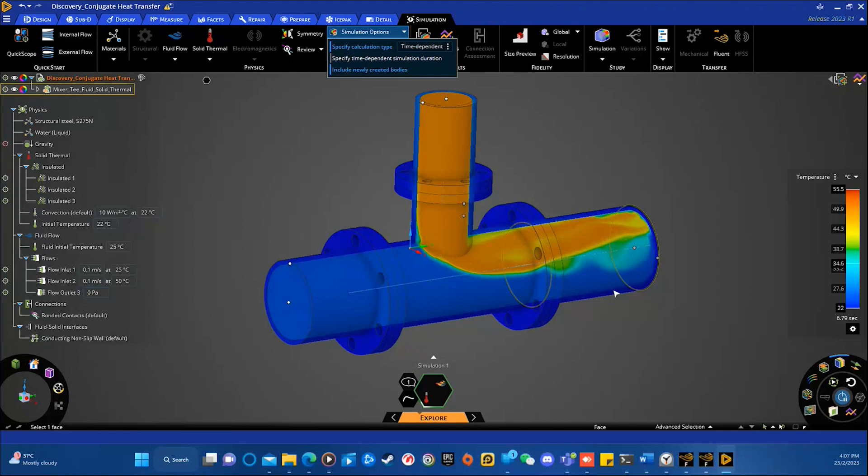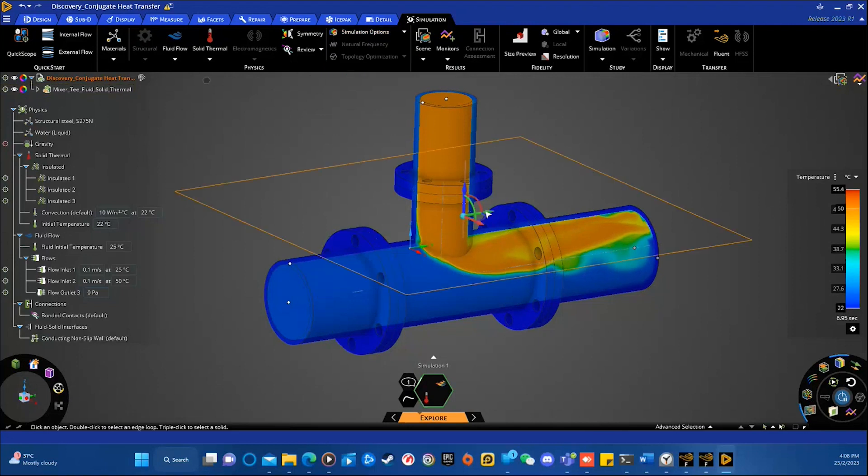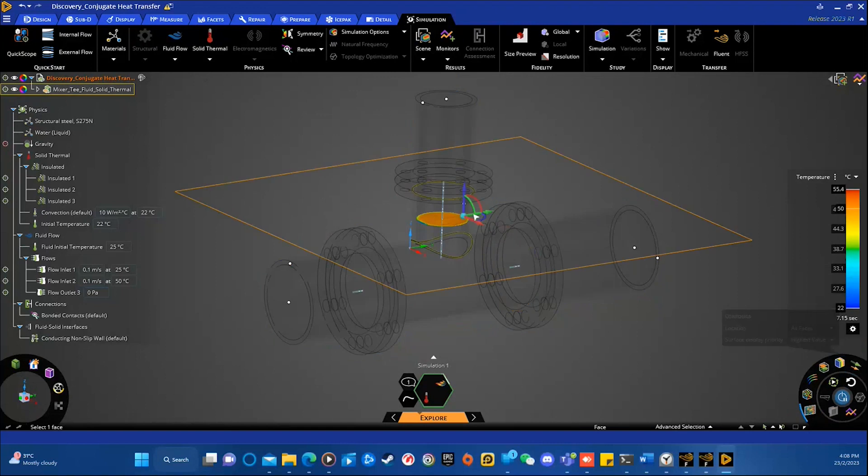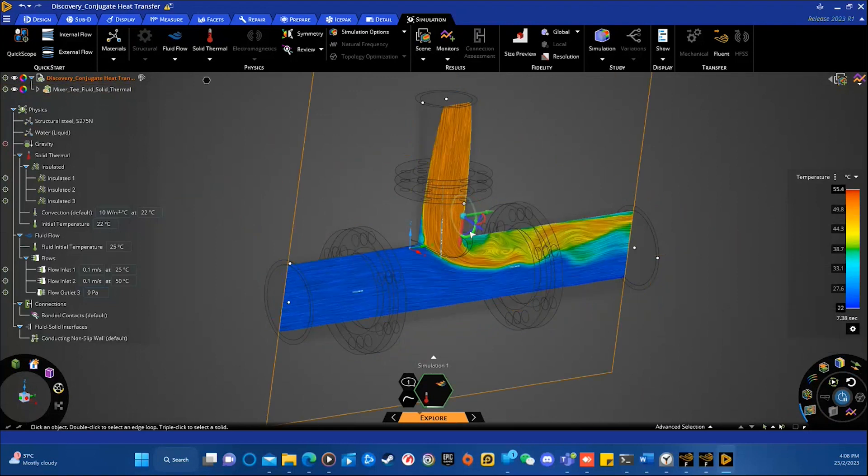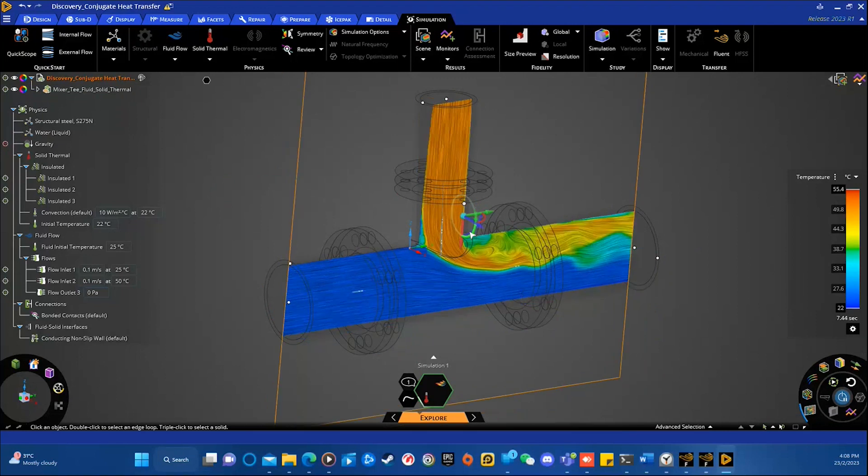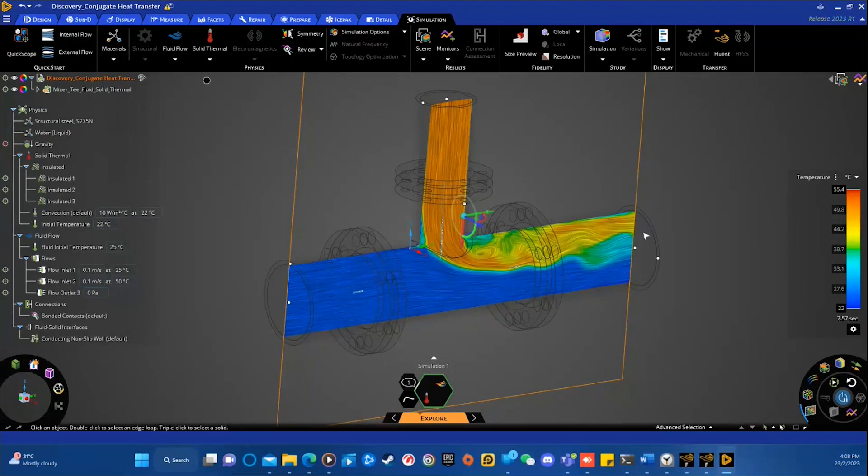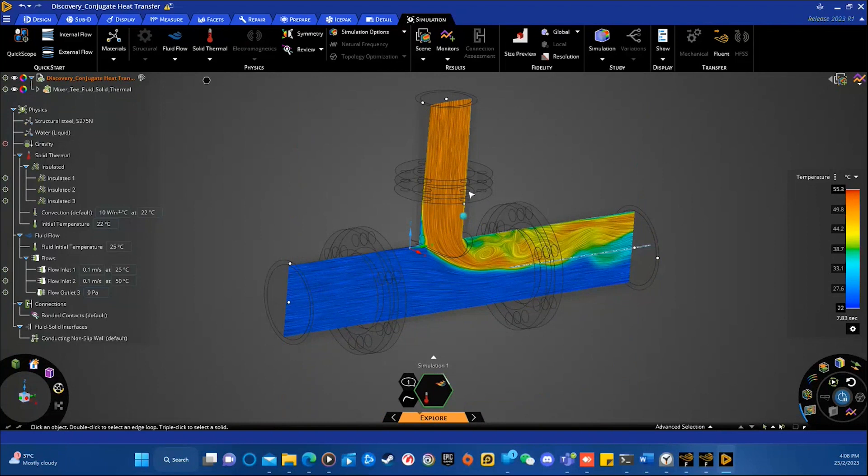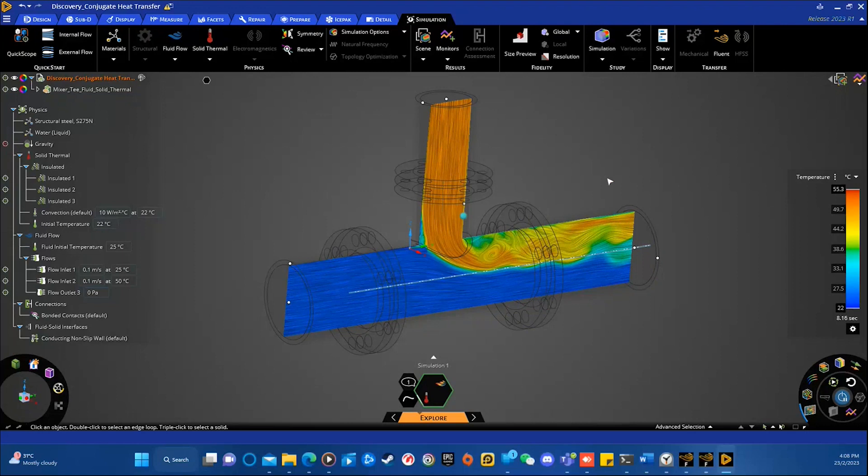As you can see, the mixing condition is actually quite concerning. You can see the mixing condition is actually not that good. Because you can see the outlet flow is mostly cold. So, to improve the mixing, maybe you can add in some baffles or obstructions to increase the turbulence.